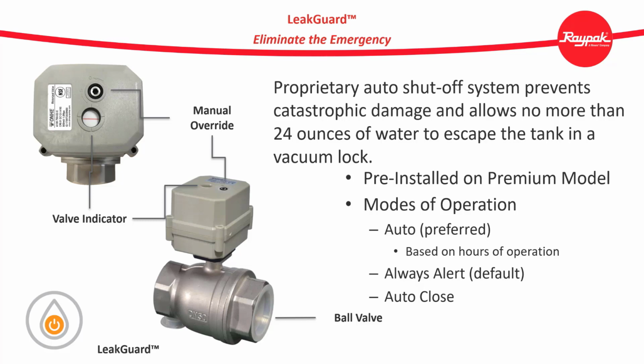In auto close mode, the Triton will alarm and close the valve. This will create a vacuum in the tank as we stop feeding the leak. We did a lot of testing, and the most water that was ever lost was only 24 ounces.